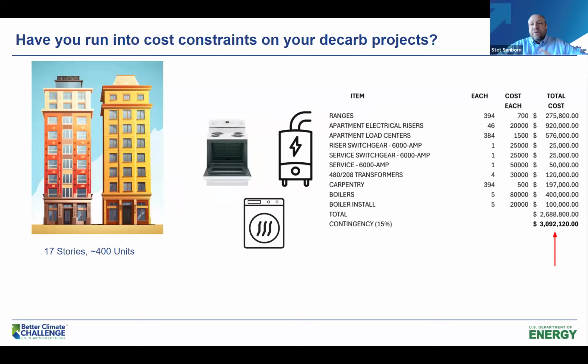So you can see from a cost standpoint, these 3 things that they were trying to do: an electric range, electric boilers for the central plant, and electric dryers, had a substantial cost impact to this project. Over $3 million on a 17-story, 400 unit building. That price barrier does not work for most folks, especially if the building isn't in need already of a gut rehabilitation or repositioning. So we're going to talk through how you might approach this that might bring down those costs systematically and end up still achieving GHG reductions, but without the cost burden associated with just doing one-for-one replacements.